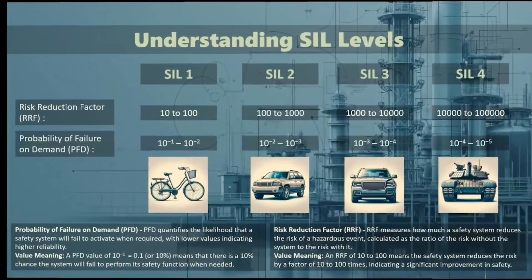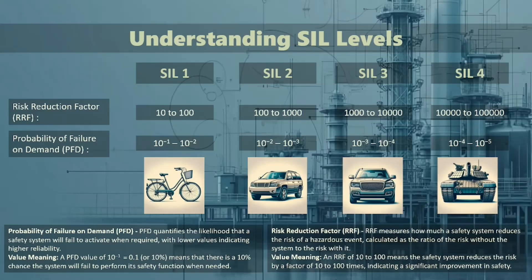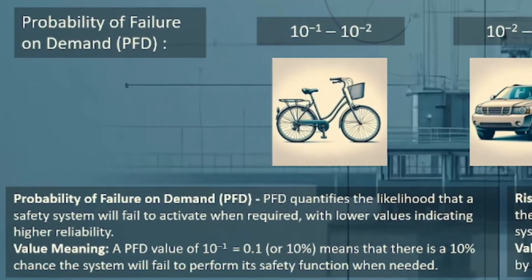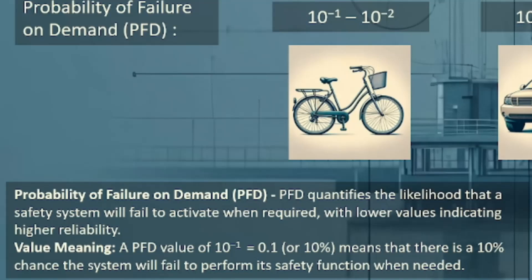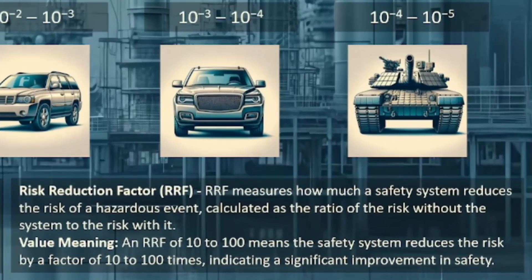Let's break down the SIL levels. Each level represents a range of risk reduction in probability of failure on demand, or PFD. Probability of failure on demand quantifies the likelihood that a safety system will fail to activate when required, with lower values indicating higher reliability. A PFD value of 0.1, or 10%, means there is a 10% chance the system will fail to perform its safety function when needed. Risk reduction factor, or RRF, measures how much a safety system reduces the risk of a hazardous event, calculated as the ratio of the risk without the system to the risk with it. An RRF of 10 to 100 means the safety system reduces the risk by a factor of 10 to 100 times, indicating a significant improvement in safety.